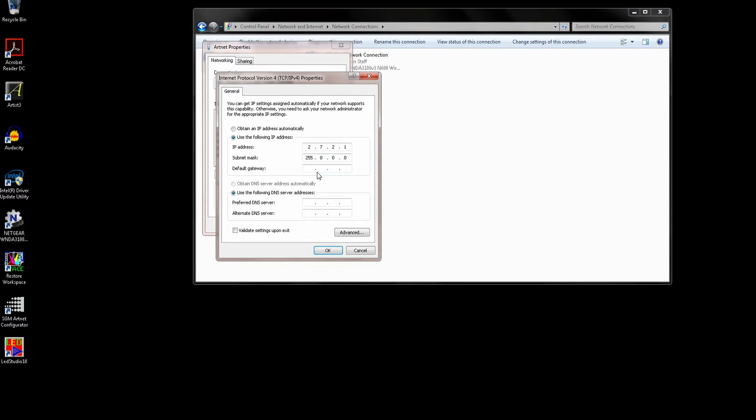And this would be fine if we were connecting to say a router which has its own Dynamic Host Configuration Protocol or DHCP server built in. We however want to explicitly specify the IP address of this network card so we can talk to the A4. So here I've given it an address of 2.7.2.1. As long as the first number is 2, it doesn't matter what the other numbers are as long as they are between 0 and 255 and the entire address is unique on your network.